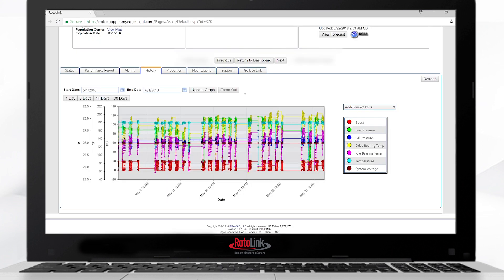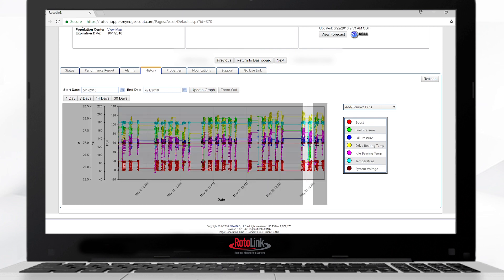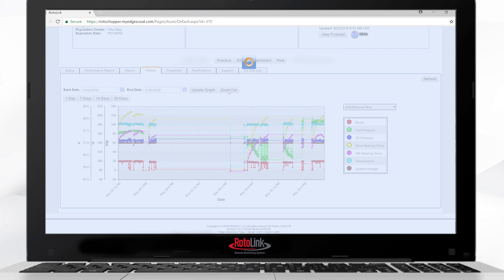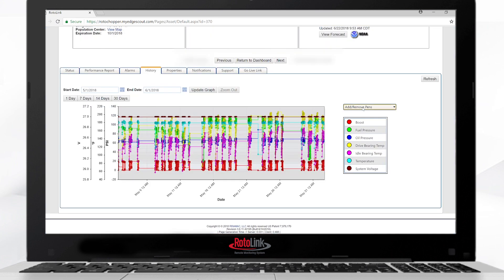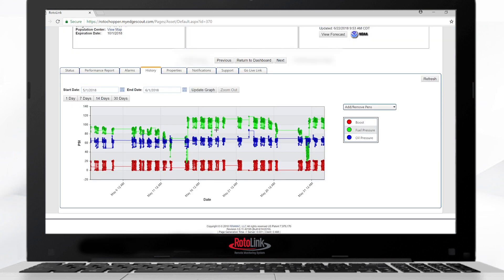So here is an example of how we can use rotolink data history to view fuel pressure. On the graph, we have 30 days of data, which can get very complicated, but I can see here there is an anomaly. So I can zoom in, see that the fuel pressure has dropped very low. So if I zoom back, I can remove pens and some of the data to see more clearly what is going on. Normal operating fuel pressure should be 90 to 100 psi. And here we can see the fuel pressure has been good. But as we get further down the graph here, we have lost fuel pressure. The operator simply replaced the fuel filters. Fuel pressure came back up to 100 psi and everything was operating as normal.